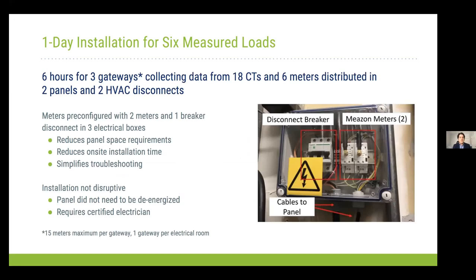Great. I want to talk a little bit about installation now. An electrician performed the installation within a day. We installed this equipment in 6 different loads, and it took the electrician 6 hours for 3 gateways that were connected to 18 current transformers and 6 meters distributed in 2 panels and 2 HVAC disconnects, by the way. What you see on the right side is a close-up picture of the meters. This box over here was pre-configured by the distributor, and the reason we did that is because it saved a lot of time in installation. So this was shipped to us already set up like that. That definitely saved us some time because an electrician didn't have to do that.